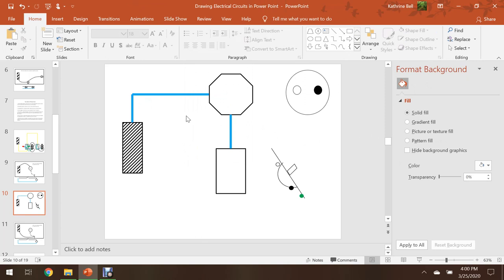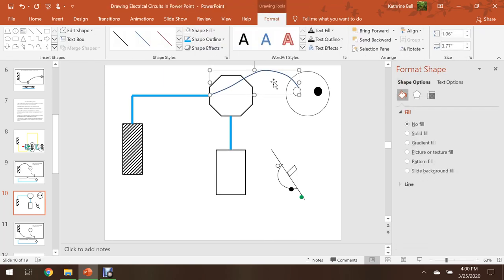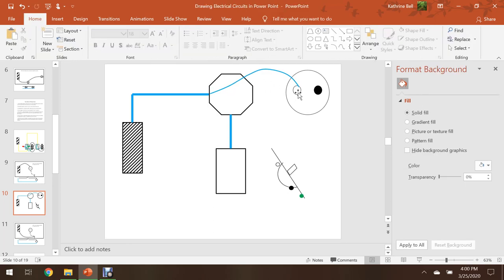All right, we're going to follow the basic rules of wiring again. We're going to start with our grounded or neutral conductor. I'm going to go to insert and shape. I'm going to check curve. Now, a switch does not utilize current. A switch is just a gate. It only opens and closes, make or break a circuit. So in this case, my white insulated conductor coming from the source is going to go and just connect directly to the silver terminal on the keyless light. That doesn't mean that we don't have a white conductor between the light and the switch. It just means that it's going to be used for a different purpose.